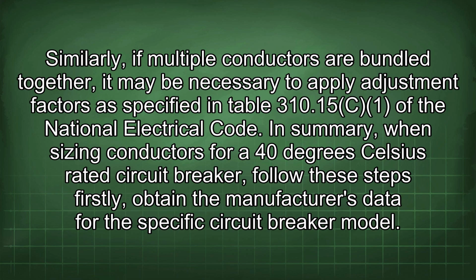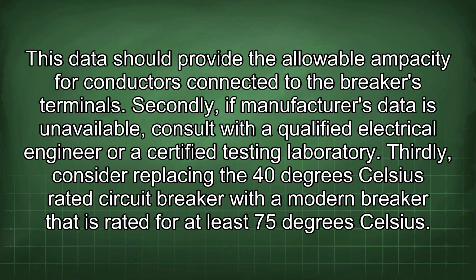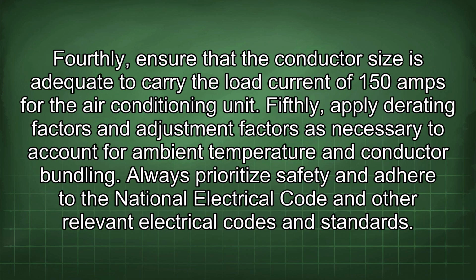In summary, when sizing conductors for a 40 degrees Celsius rated circuit breaker, follow these steps. Firstly, obtain the manufacturer's data for the specific circuit breaker model. This data should provide the allowable ampacity for conductors connected to the breaker's terminals. Secondly, if manufacturer's data is unavailable, consult with a qualified electrical engineer or a certified testing laboratory. Thirdly, consider replacing the 40 degrees Celsius rated circuit breaker with a modern breaker that is rated for at least 75 degrees Celsius. Fourthly, ensure that the conductor size is adequate to carry the load current of 150 amps for the air conditioning unit.